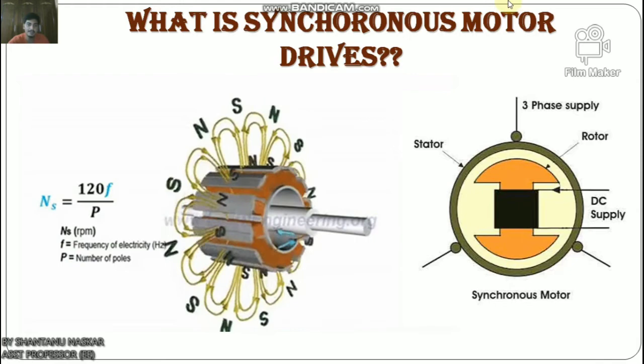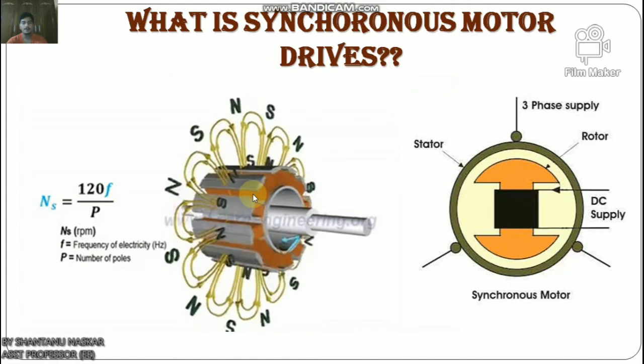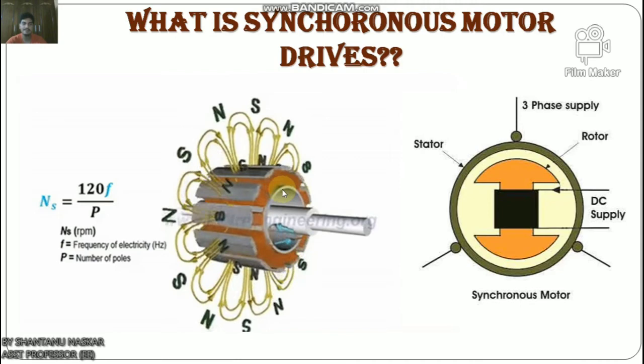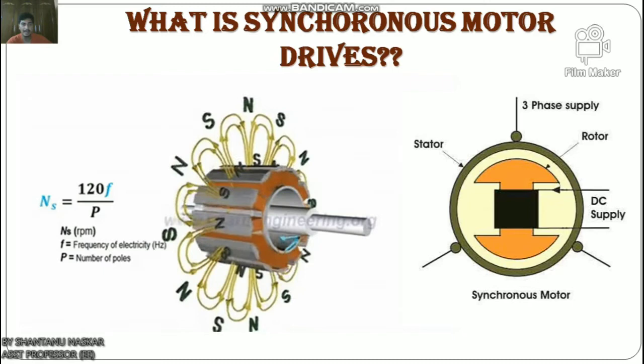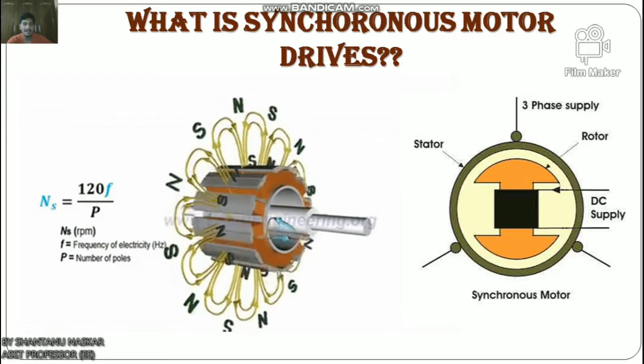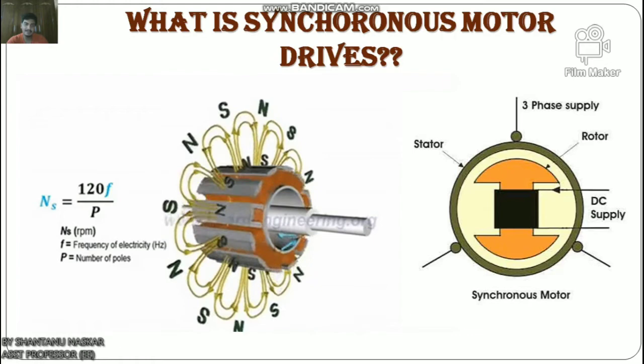Now let us discuss pull-in of the synchronous motor. When the rotor reaches near synchronous speed, the DC field supply is switched on and the pull-in process begins. During switching on, due to phase angle and torque angle, various disturbances occur in the motor, and several slips of air gap flux are also seen. As the pull-in process is completed, the rotor acquires synchronous speed. To complete pull-in as fast as possible, the DC supply should be switched on at the most favorable angle.